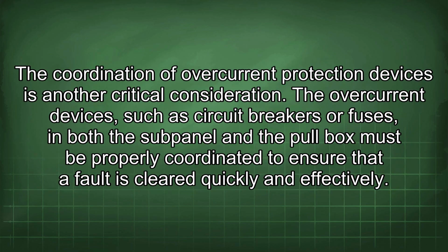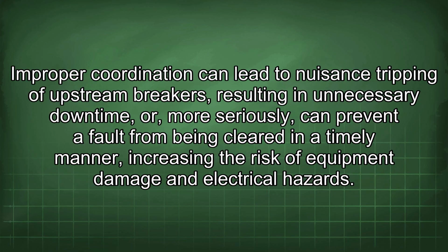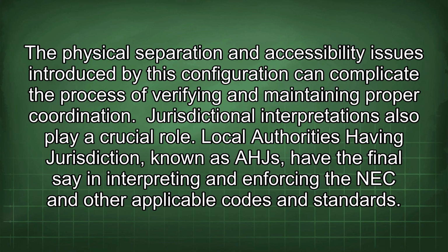The coordination of overcurrent protection devices is another critical consideration. The overcurrent devices, such as circuit breakers or fuses, in both the subpanel and the pull box must be properly coordinated to ensure that a fault is cleared quickly and effectively. Improper coordination can lead to nuisance tripping of upstream breakers, resulting in unnecessary downtime, or, more seriously, can prevent a fault from being cleared in a timely manner, increasing the risk of equipment damage and electrical hazards. The physical separation and accessibility issues introduced by this configuration can complicate the process of verifying and maintaining proper coordination.